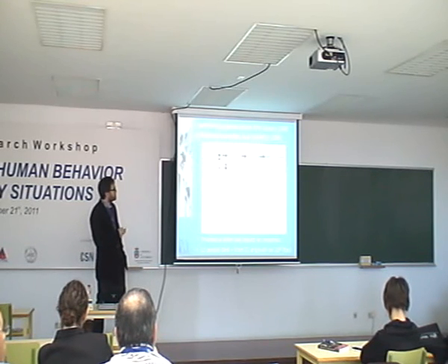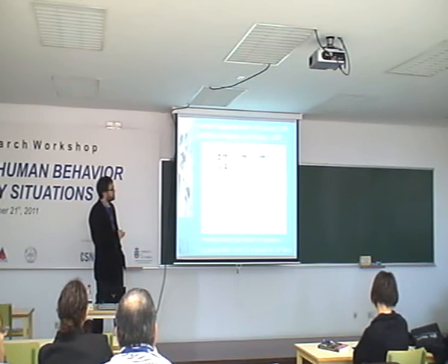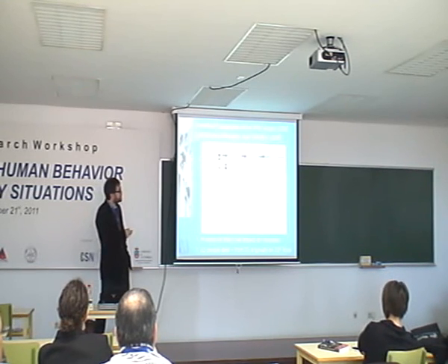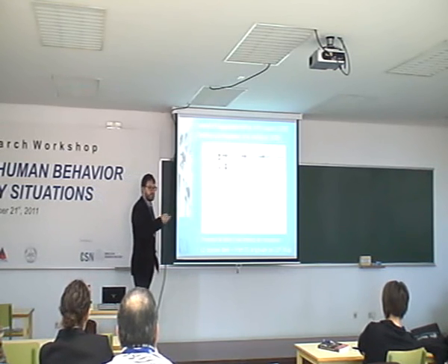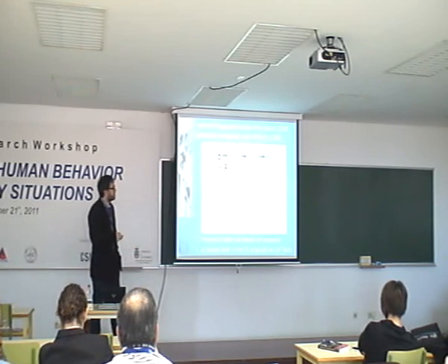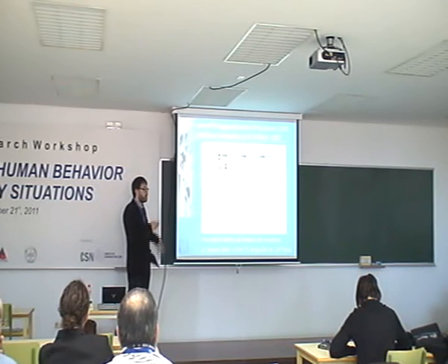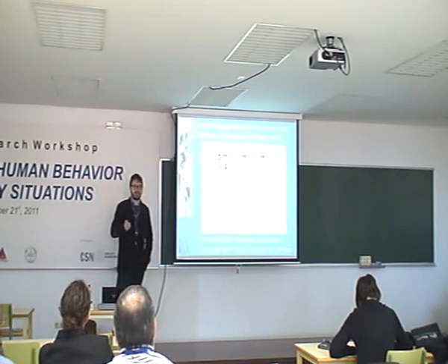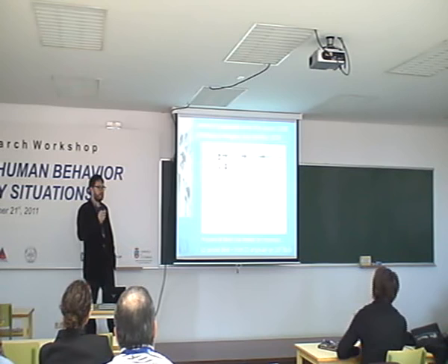So, a fire was detected at 12:32 on floor 4. A signal from a detector was sent to a command and control office on the 5th floor. This then contacted the officer on floor 4 to confirm that it was a real fire. So there was a confirmation step. This was confirmed, and then the officer on floor 4 commenced the evacuation of that floor, the fire floor. The officer on floor 5 in the command centre attempted to contact a senior member of staff to get guidance, and he did this by a coded message.